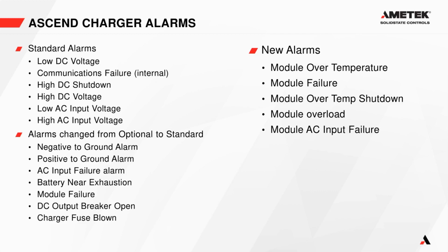But now we have some alarms that were optional on the old DCR product that are now standard on the 3-phase Ascend charger. That is our ground detect alarms, negative to ground and positive to ground, the AC input failure alarm, and the battery near exhaustion alarm. We have a module failure alarm to let you know that one of the modules in the system has failed. And then we have the DC output breaker open alarm, and that aux contact is always in the system for the DC output breaker's position. And then we have a charger fuse blown alarm.